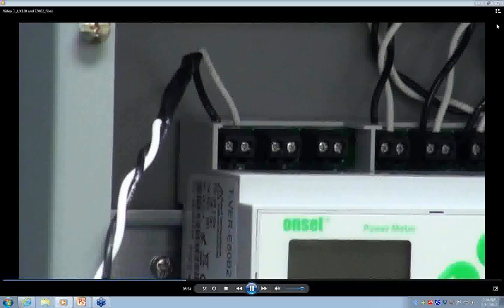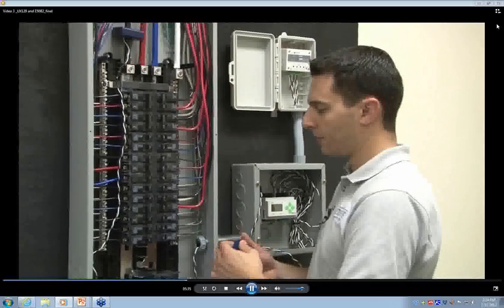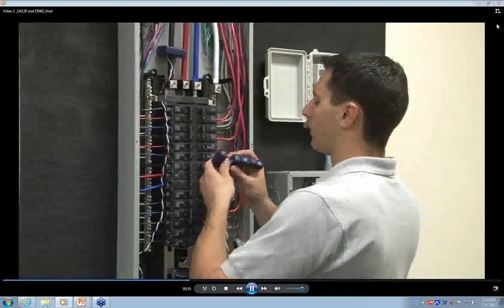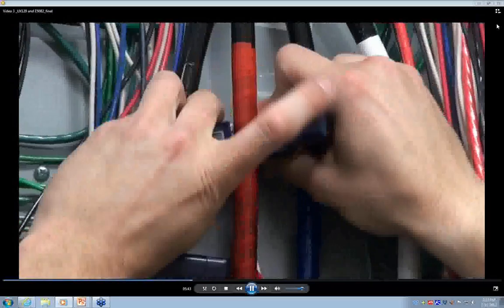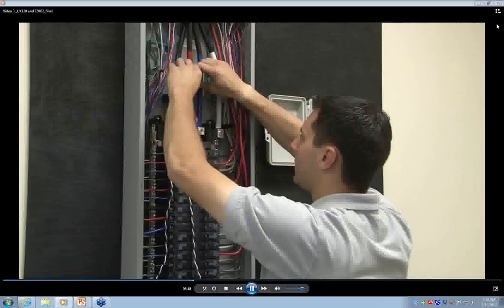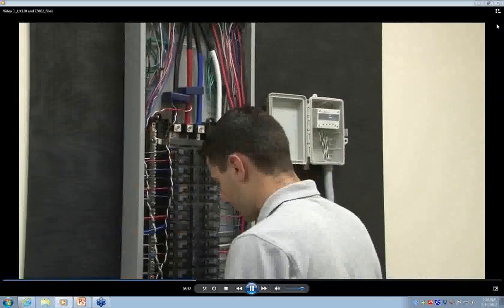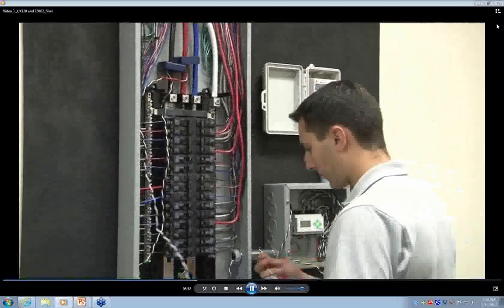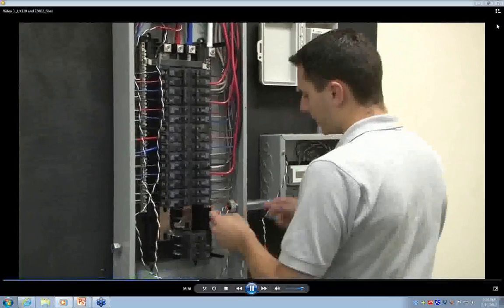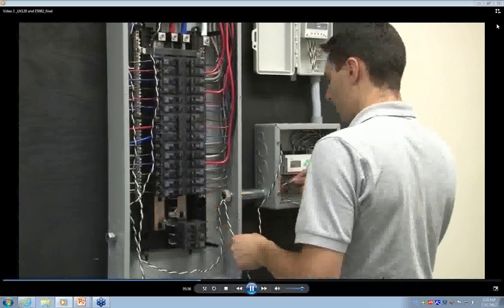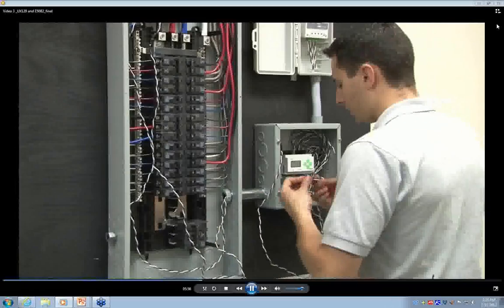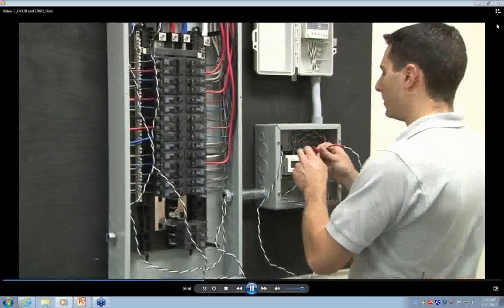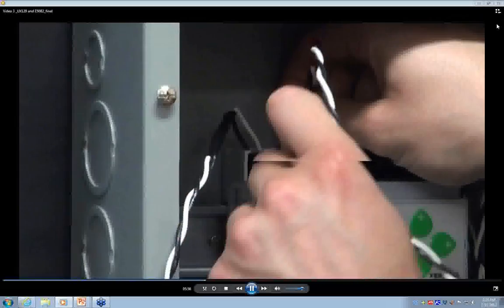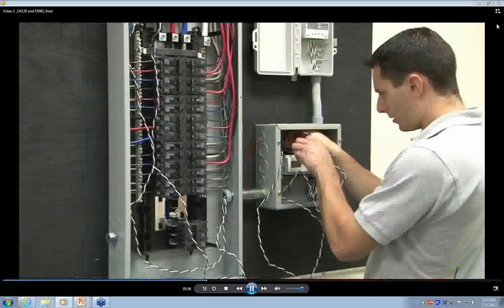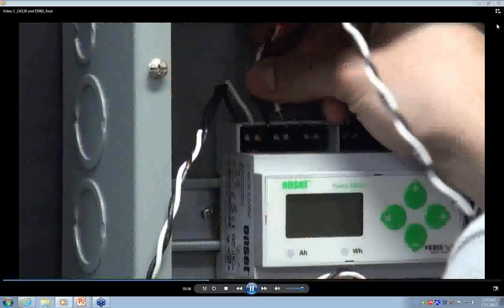We'll now connect the red phase B CT to phase B of our panel. Once again, we make sure the arrow faces the source, and we clip the CT closed. We pull the CT conductor through the conduit and connect this to the phase B CT terminal on the E50B2. The black conductor connects to the negative terminal, and the white conductor connects to the positive terminal.